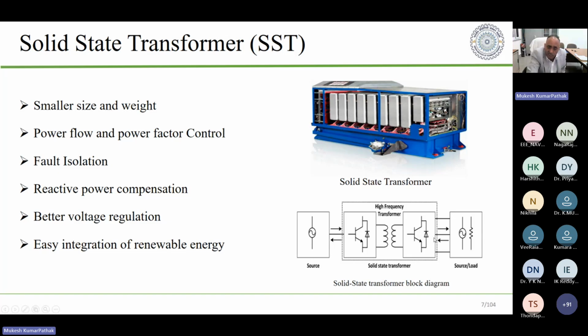When these transformers are installed in a substation, they will provide an easy way of renewable integration, because this transformer will also have a DC port, sometimes a high voltage DC port, sometimes a low voltage DC port, or sometimes both. Renewable energy sources can be connected to these transformers directly. The converter that a renewable source requires of its own, that additional converter will not be required. You can directly connect it to the grid through the solid state transformer.